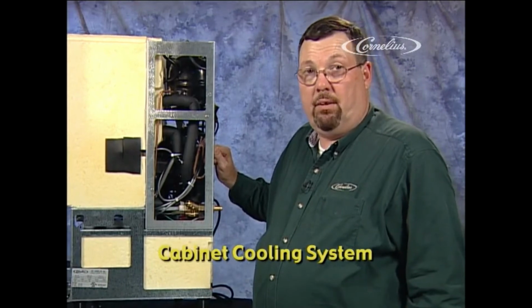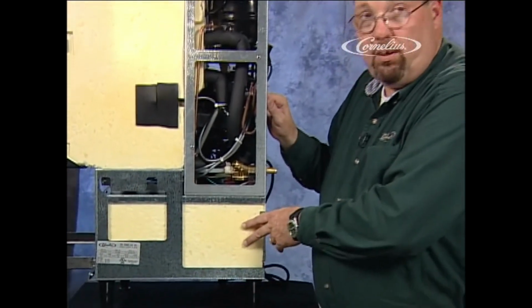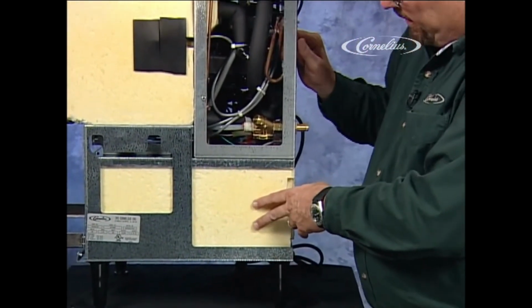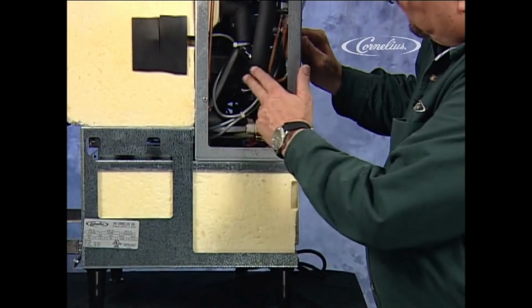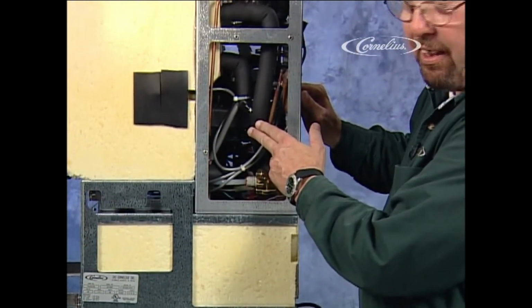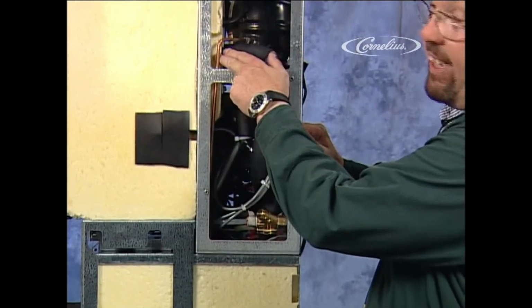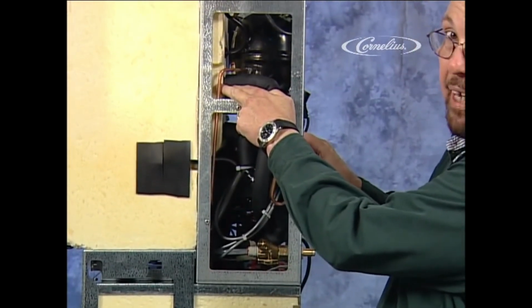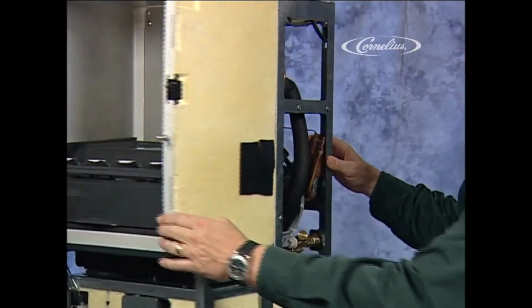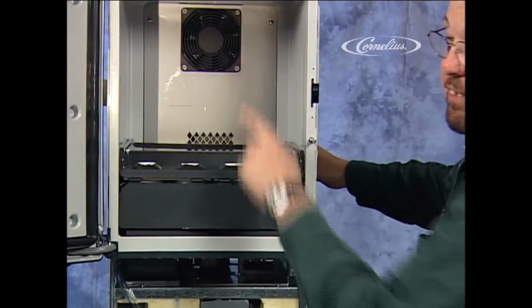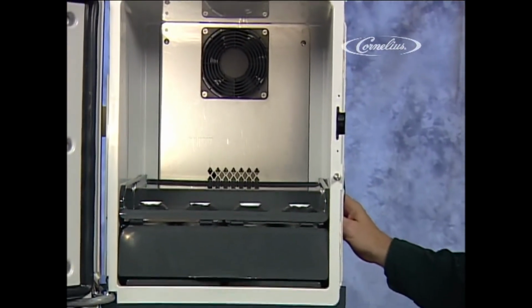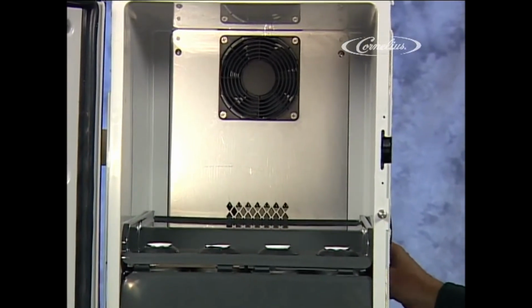The other critical piece of the cooling system in the Quest dispenser is the cabinet cooling system. We take the 32 to 33 degree water out of the water bath tank and we circulate it up through these lines by means of the pump agitator motor. It goes then into a heat exchanger which is located in the back of the cabinet. In front of that heat exchanger is a fan. This fan then circulates the cold air through the cabinet, keeping it at 40 degrees.